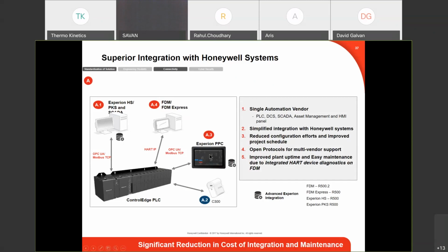And then one cool thing that we've added here is this Experion panel PC as a perfect match. With this Experion panel PC, I can connect it directly to the PLC. You have the same graphics that you would see in the control room. It's one shared repository, connected to the FTE. I can also view all the diagnostics coming off the PLC, and all of the graphics that are tied to the PLC peer-to-peer, meaning that when I build the logic inside this PLC, either if I use this panel PC or Experion PKS, I can push one button. It's called Publish to Experion, and I'll show you that here shortly. It will publish all of the tags that I wrote in this PLC to Experion automatically.